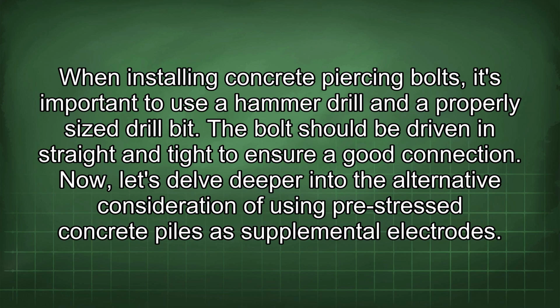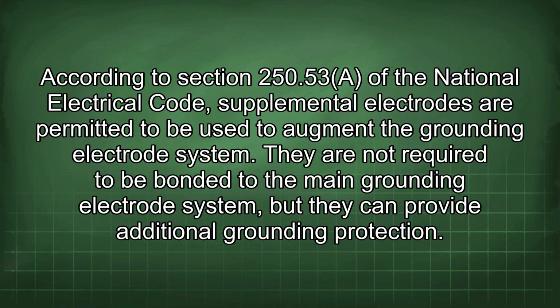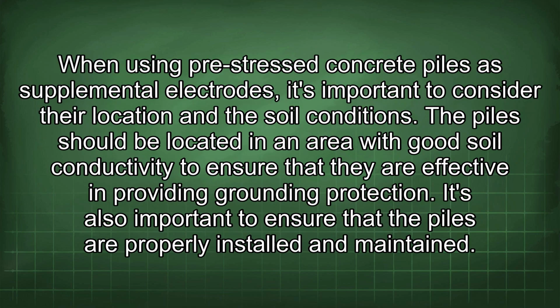Now let's delve deeper into the alternative consideration of using pre-stressed concrete piles as supplemental electrodes. According to Section 250.53 of the National Electrical Code, supplemental electrodes are permitted to be used to augment the grounding electrode system. They are not required to be bonded to the main grounding electrode system, but they can provide additional grounding protection. When using pre-stressed concrete piles as supplemental electrodes, it's important to consider their location and the soil conditions. The piles should be located in an area with good soil conductivity to ensure that they are effective in providing grounding protection. It's also important to ensure that the piles are properly installed and maintained.